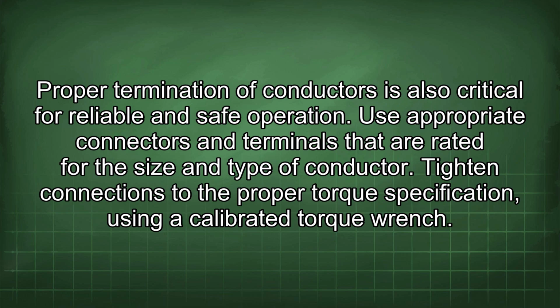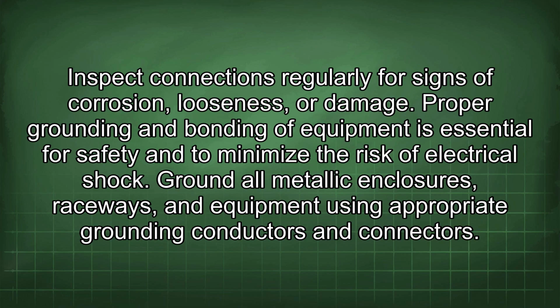Use appropriate connectors and terminals that are rated for the size and type of conductor. Tighten connections to the proper torque specification using a calibrated torque wrench. Inspect connections regularly for signs of corrosion, looseness, or damage.